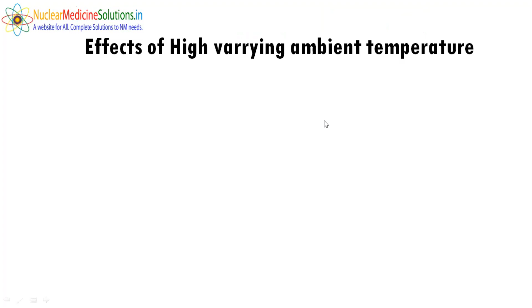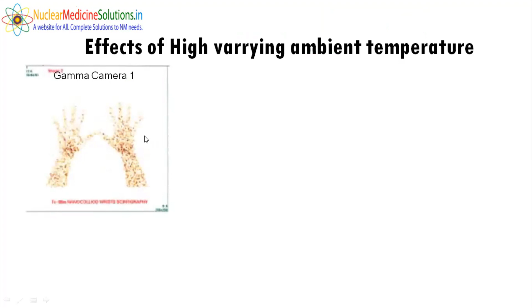Your ambient temperature should also remain within 20 to 30 degrees centigrade. If it is high, then it will degrade your image quality or your uniformity. You can see here, when the temperature is around 20 degrees centigrade, it shows a good quality image. When the temperature becomes more than 22 degrees centigrade, around 26 degrees centigrade in the gamma camera 2 room, you see that image quality is degraded.